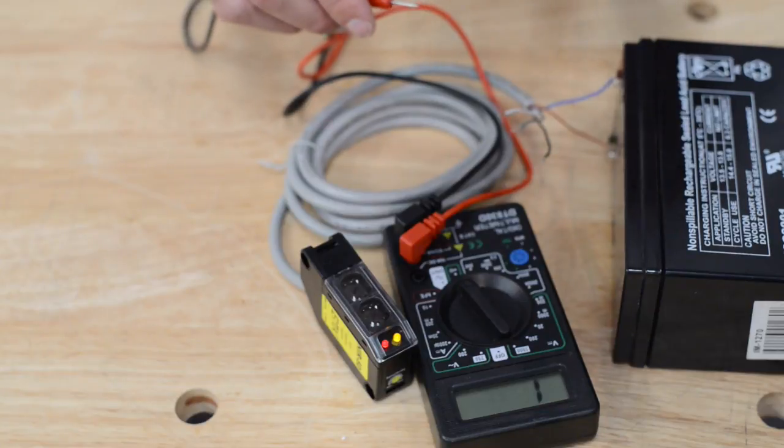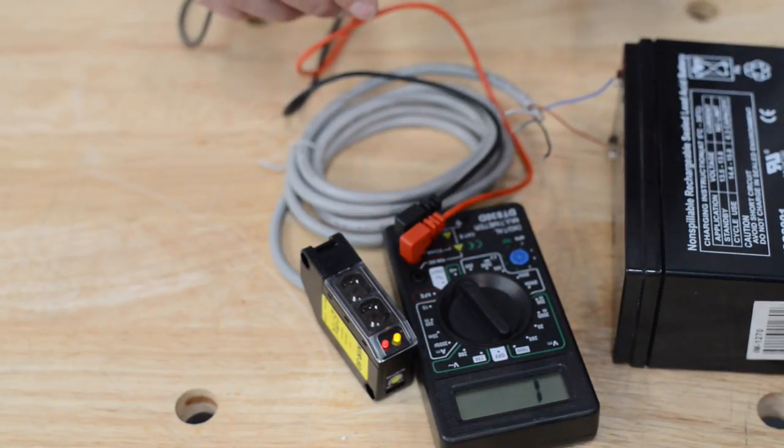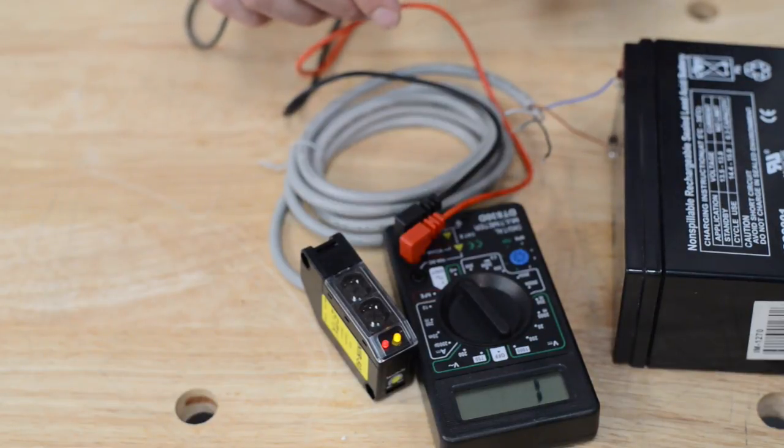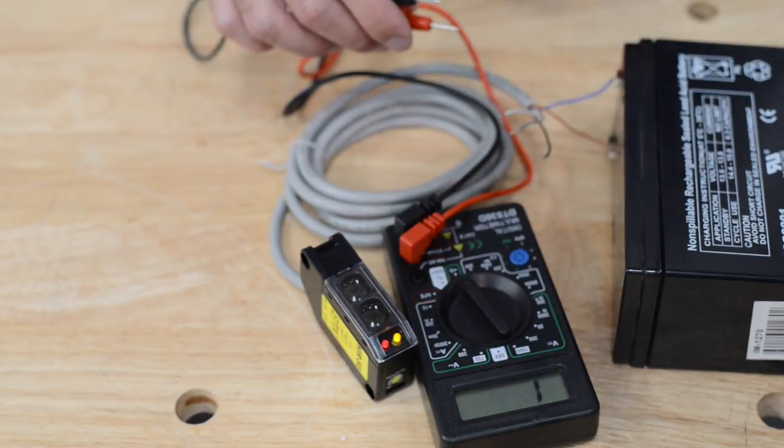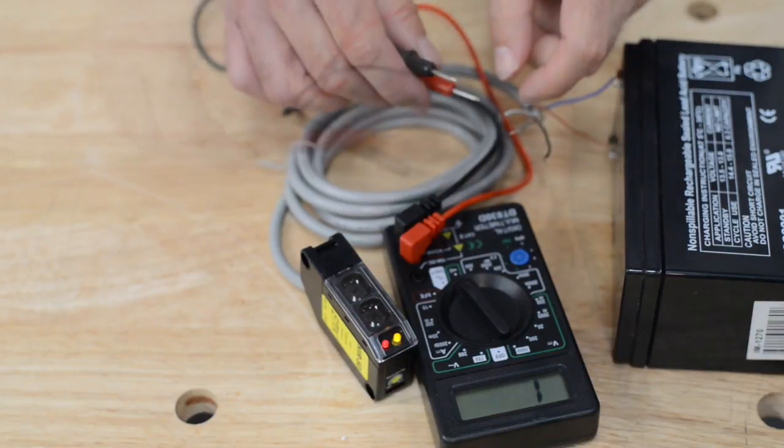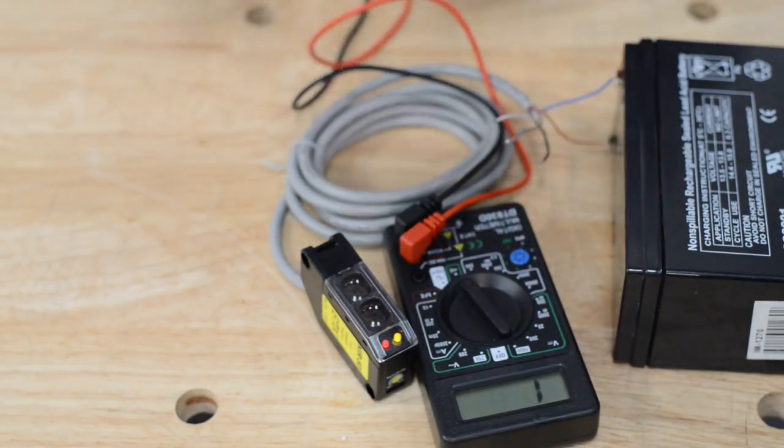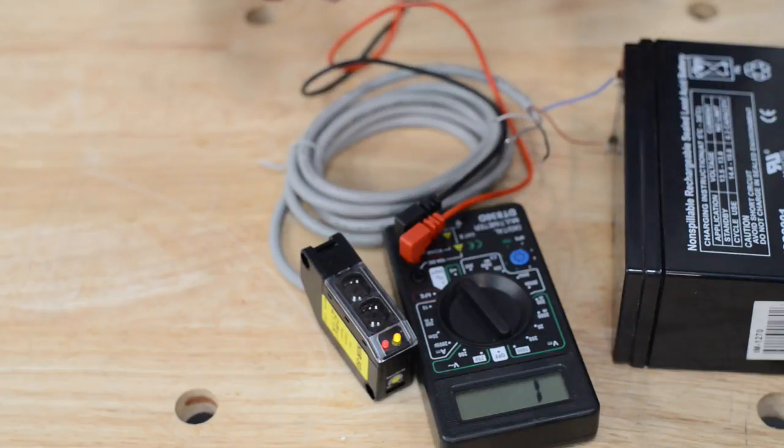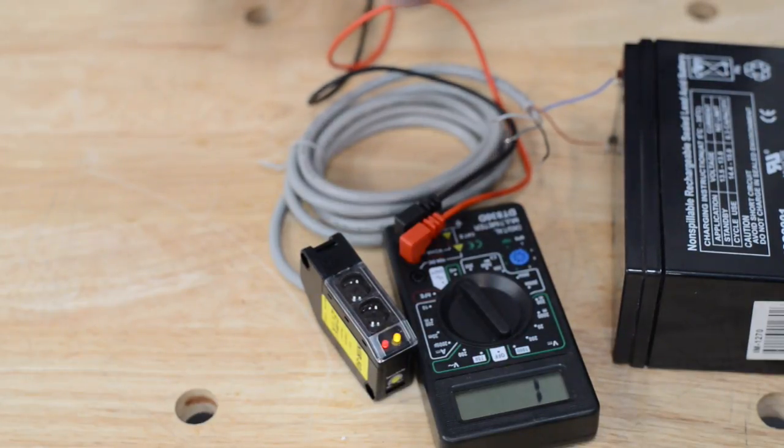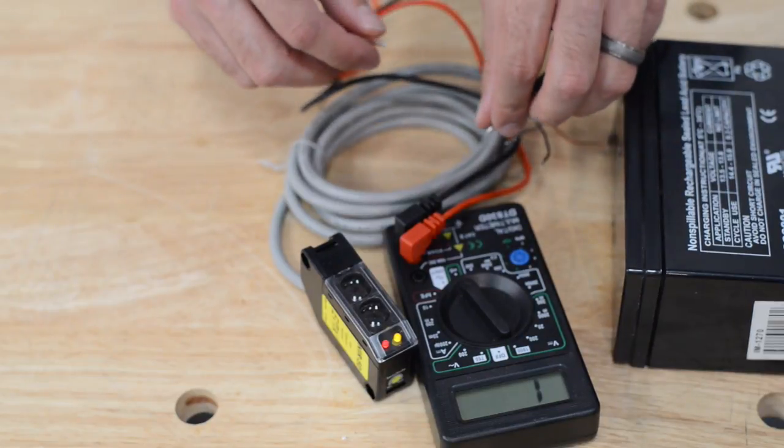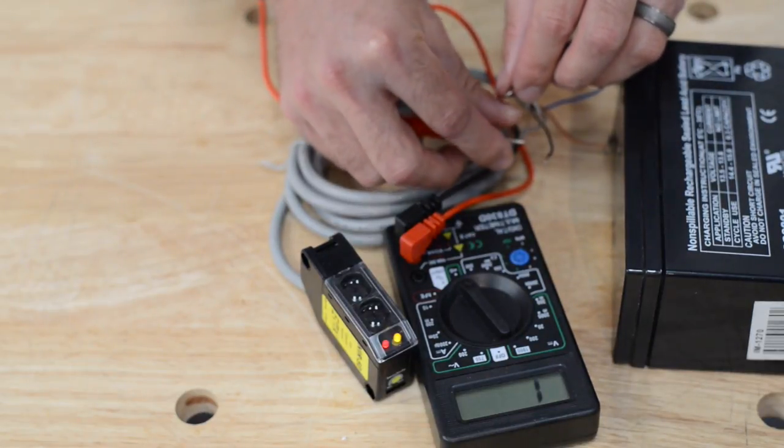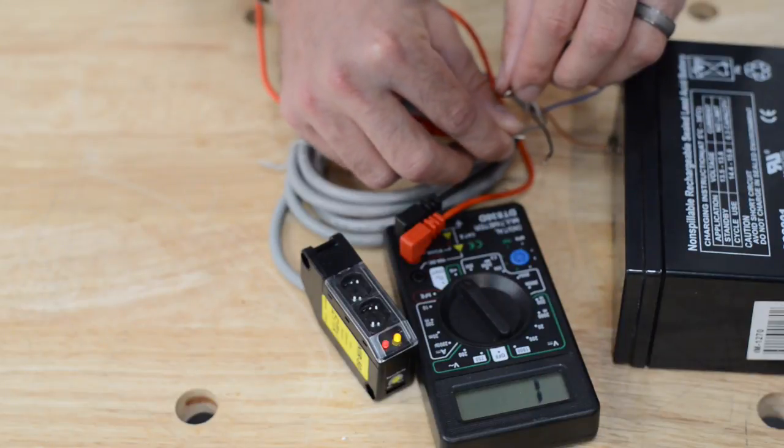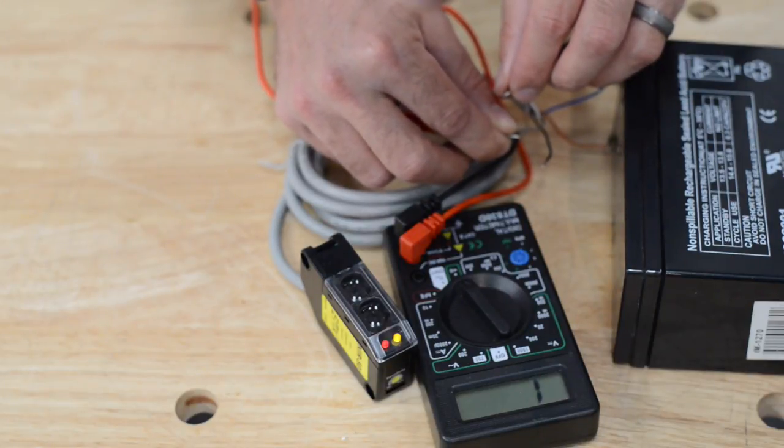First thing I'm going to do is with the beam in its default position, there should be a continuity connection between the normally closed and the common. So I'm going to find which two of these three wires has a connection. I'm going to start with the white and the gray. Now remember, I'm looking for the normally closed and the common to have continuity because the beam is currently connected. I do not have continuity between the white and the gray.